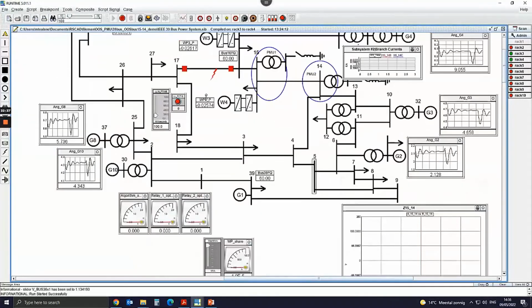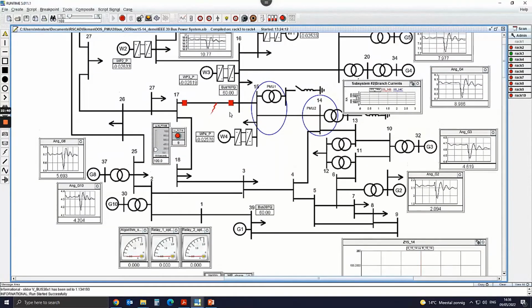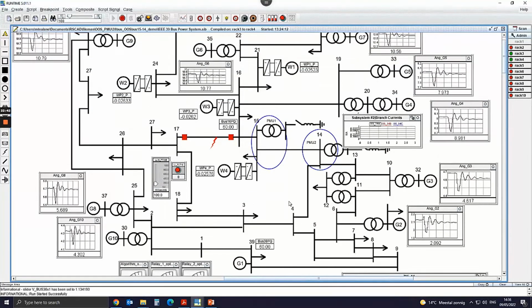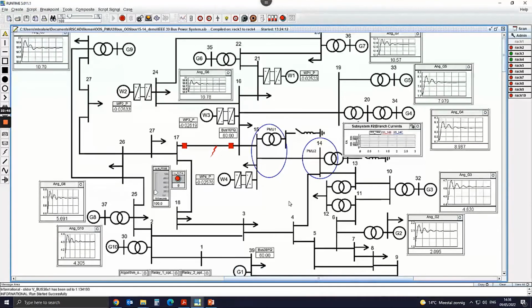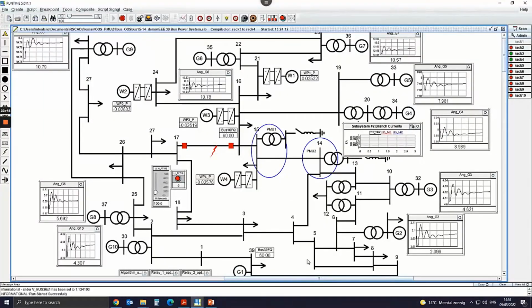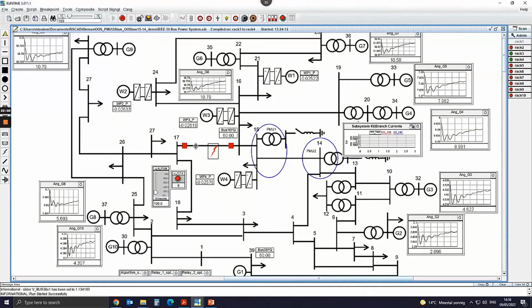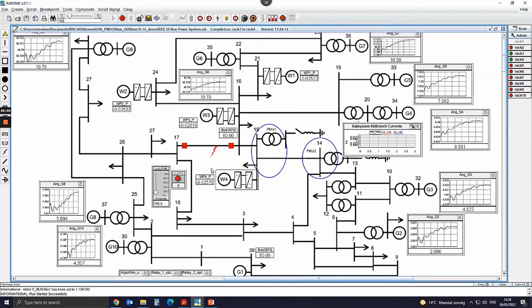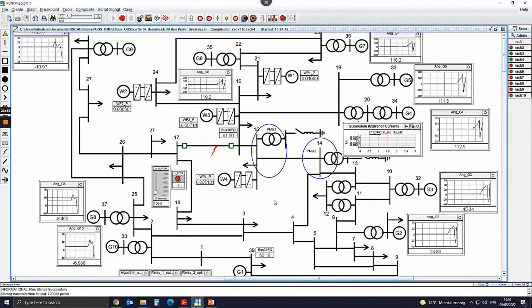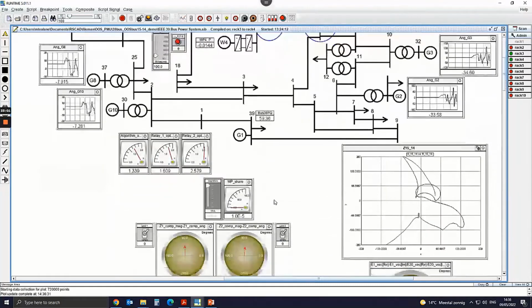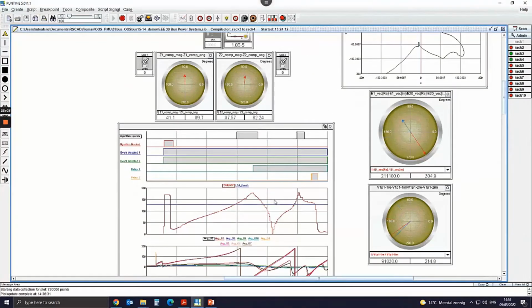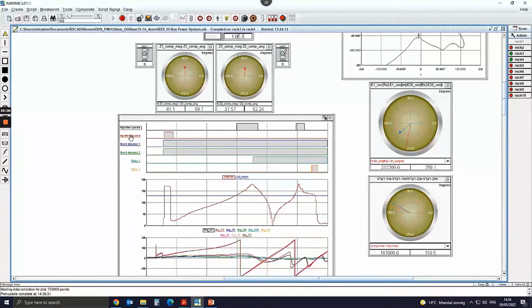Now I will create an out-of-step condition on the protected line so that we can see how the protection operates and how the impedance-based protection devices operate. The fault created here between buses 16 and 17 is 100 milliseconds long. And from this diagram here, we can see that the algorithm is blocked during the fault event, and both of the sides detect an event in the network.